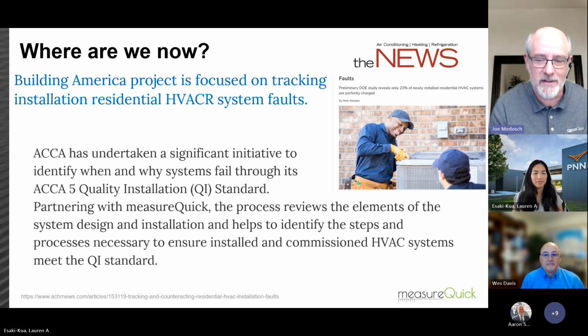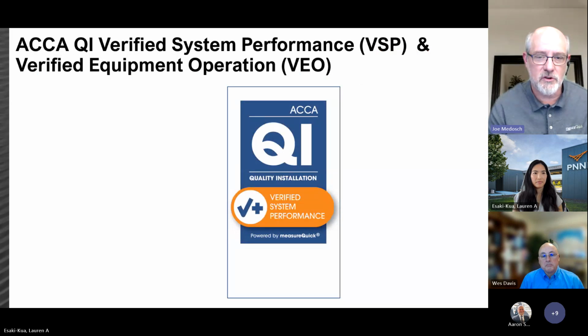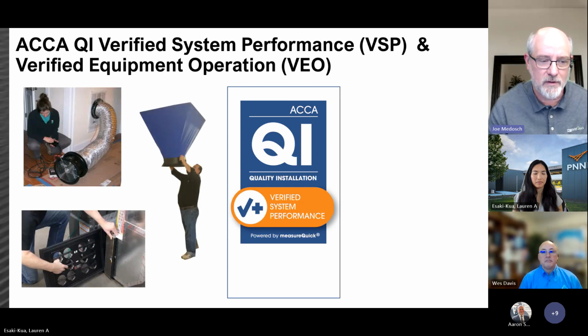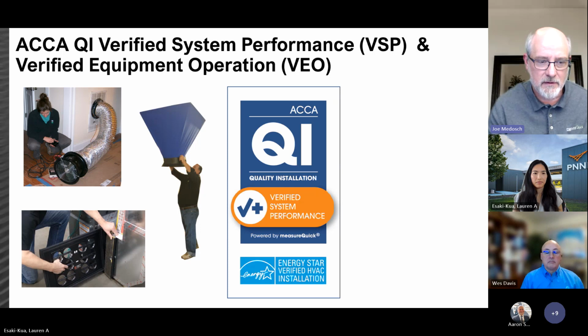This is talking about the QI standard. The challenge with the QI standard is that a lot of people mention it and talk about it, but don't really do it. It's a high level—the ultimate way you can do an install and make sure that not just the equipment was installed correctly, but the entire system was installed correctly, fully designed and implemented. Now we're able to go to MeasureQuick and combine these two. So right now we have verified system performance, which is really the QI5, and it requires some additional steps to go along with it: you must do a duct test, you must do airflow measurements, and you must do balancing.